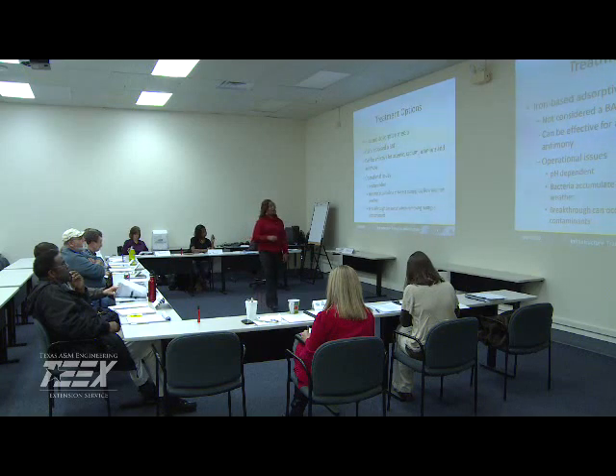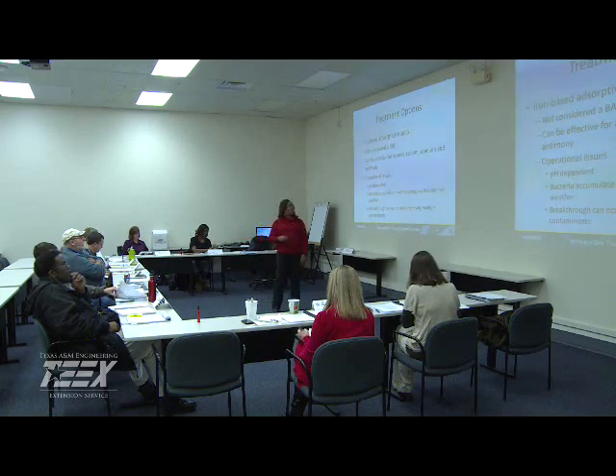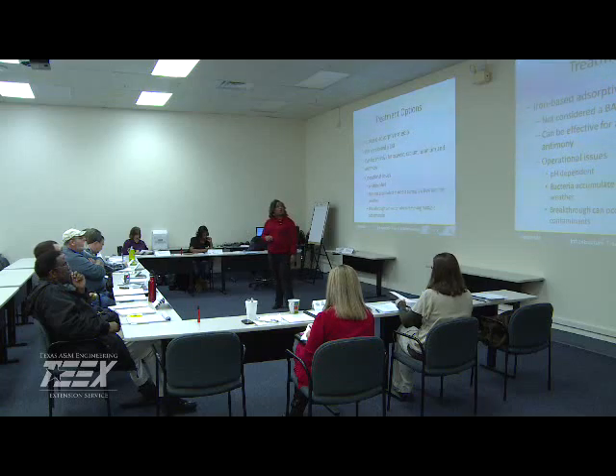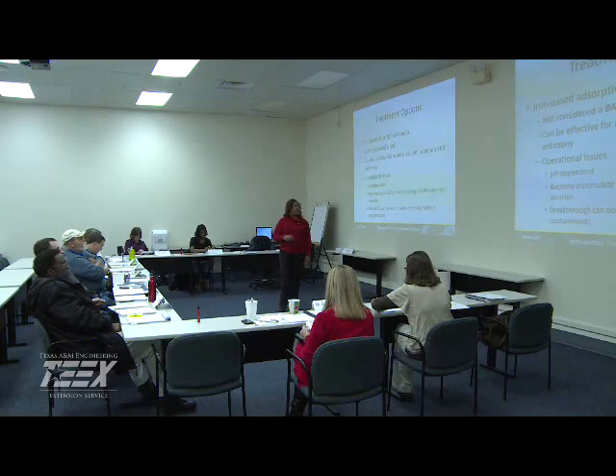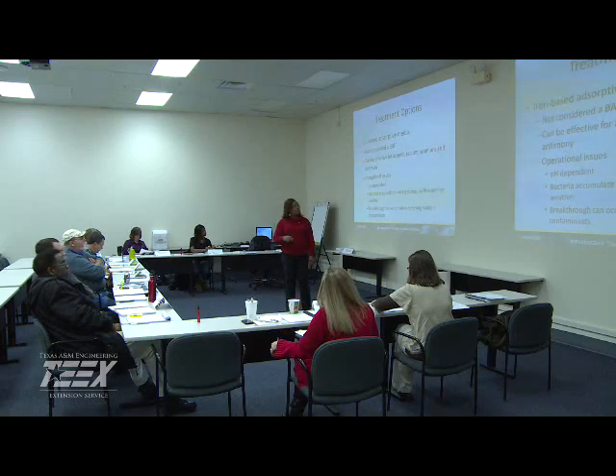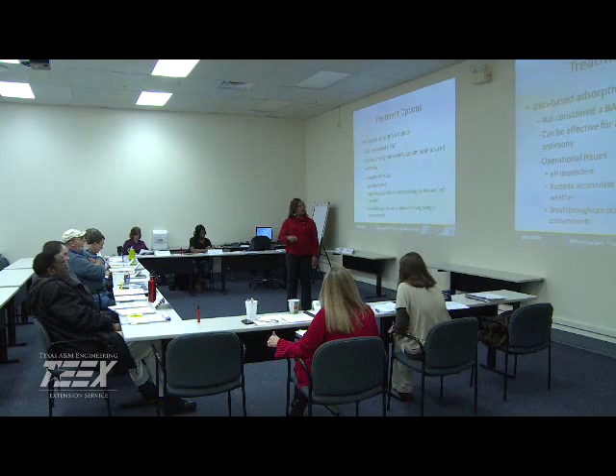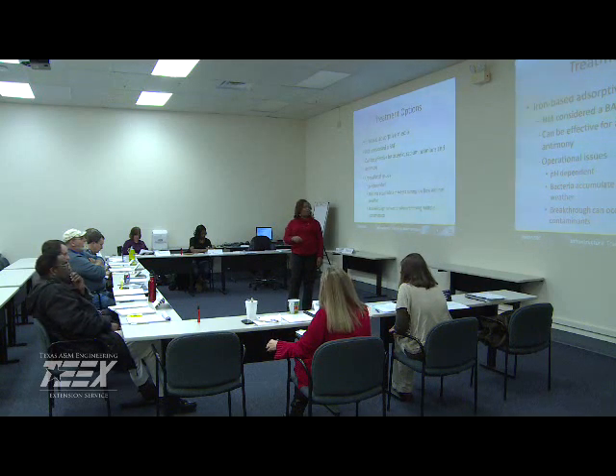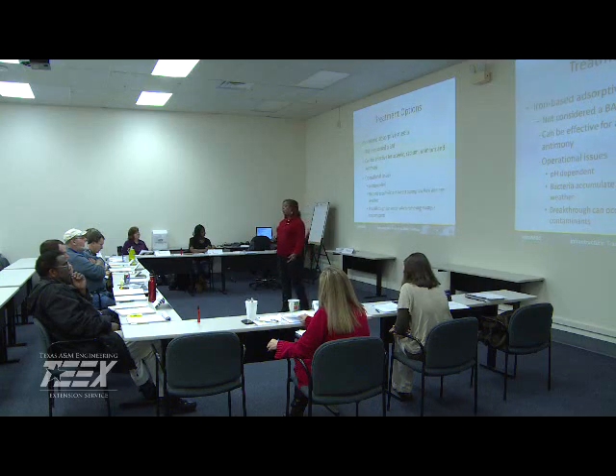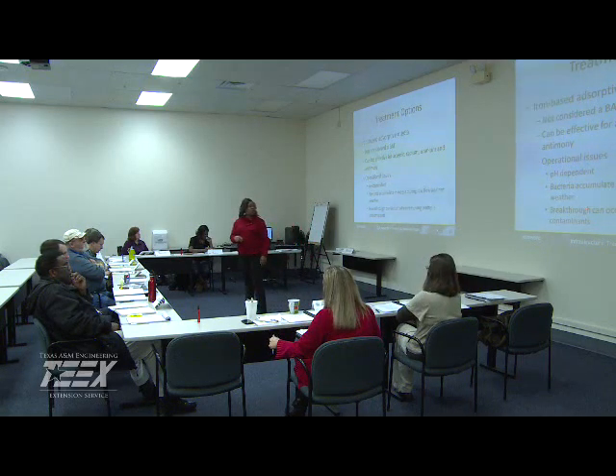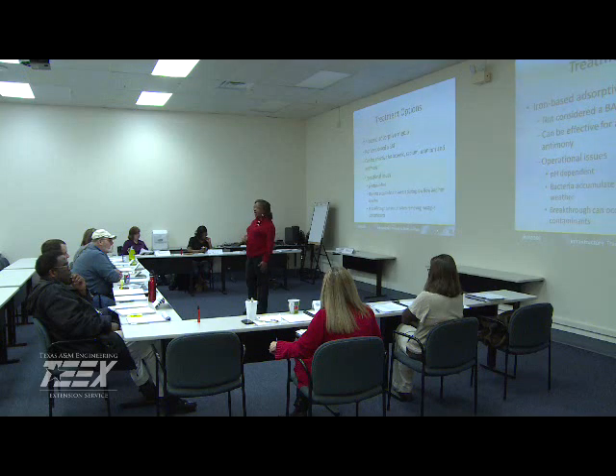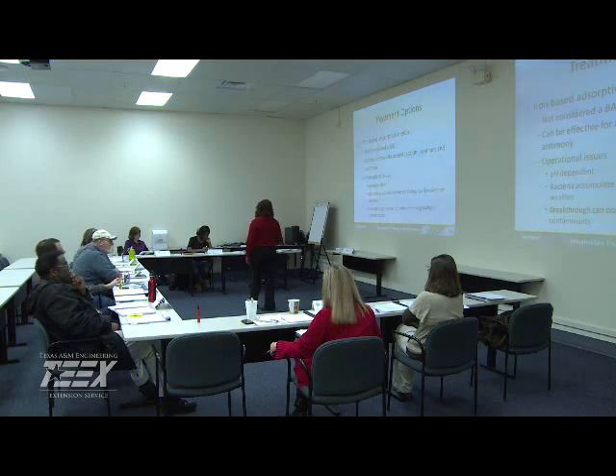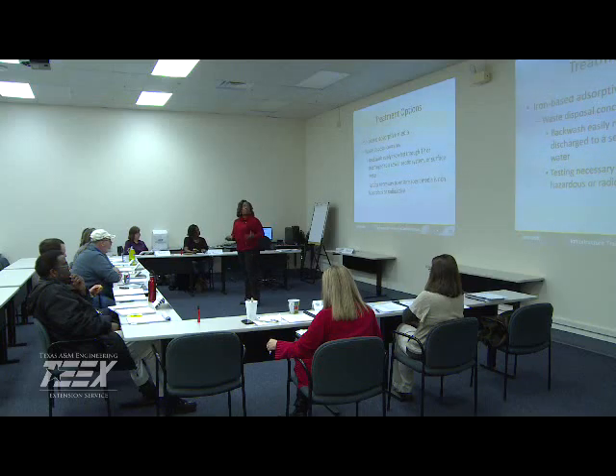Iron-based adsorptive media is another option; however, it's not considered one of the better practices or technologies available. But it can be effective for arsenic, radium, uranium, and antimony. Operational issues are similar — pH dependent. Also, you may have an accumulation of bacteria in the media during low flow or in hot weather. Breakthrough can occur when removing multiple contaminants, which could bring back the problem you had before. So you'll have to weigh the pros and the cons.